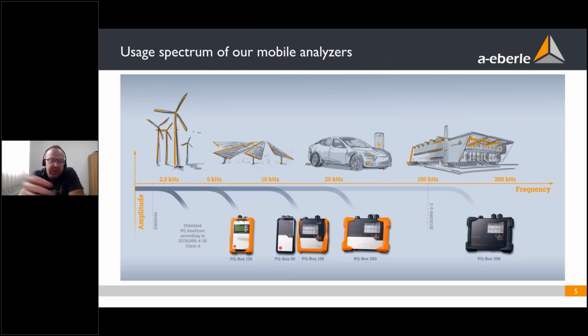So here is a range of all of our analyzers, and it's clear that with a higher number of the PQBox, the sampling frequency is higher, and we are looking at a wider spectrum. Up to 200 kilohertz is possible. So with the PQBox 150, here we're working with a sampling frequency of 20 kilohertz. So we can analyze disturbances in the grid up to 10 kilohertz.